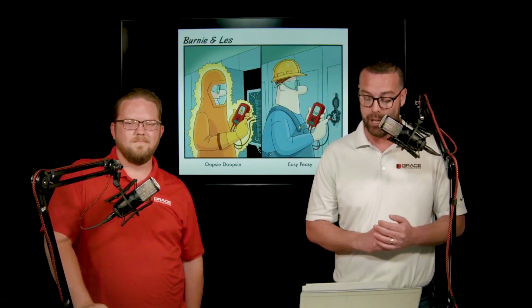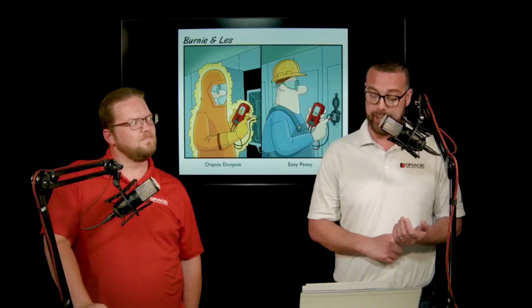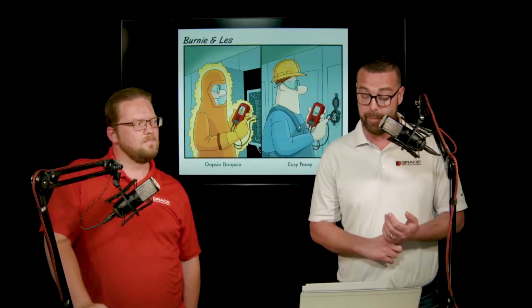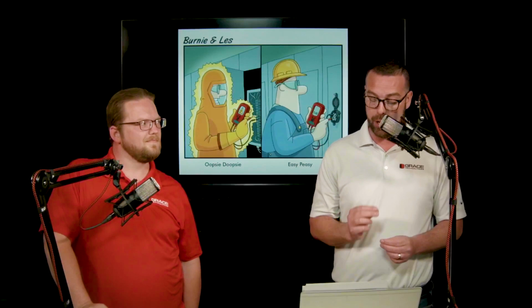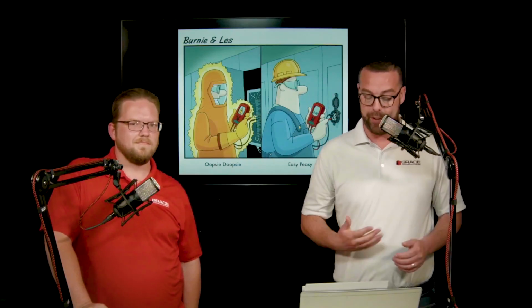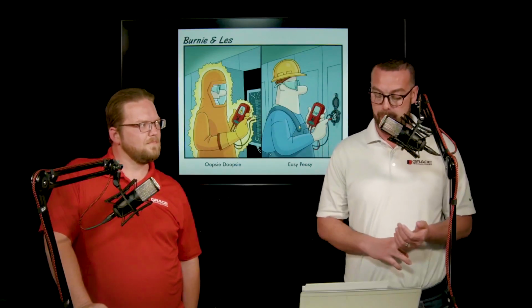Is there another reliable method for calculating the incident energy without the utility short circuit data? That's a great question, and yes, there is another method. It's called the simplified method, which can be used to calculate incident energy without relying on utility short circuit data. It utilizes available equipment and system data, such as available fault current, system voltage, and protective device characteristics, to estimate incident energy levels. While it may not provide the same accuracy as the detailed method using utility short circuit data, the simplified method can still be a reliable approach for estimating incident energy and determining appropriate PPE requirements. It's important to note that the simplified method should be used in accordance with the guidelines and limitations specified within NFPA 70E and other relevant standards and regulations. So consulting with a qualified electrical professional is recommended for accurate and appropriate incident energy calculations.